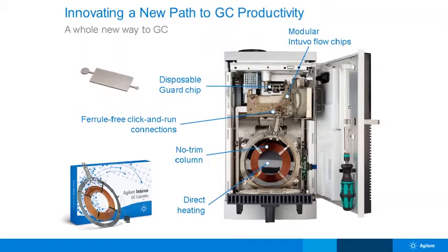And clearly this is the GC that we go to where ease of use is paramount because there's no cutting of columns, no ferrules needed here. But additional to that, when fast analysis is needed, because if you can heat at 250 degrees C per minute and also cool from 450 to 50 degrees C in less than 3 minutes, you can see why this GC has some unique abilities. Over and above that as well, we have a disposable guard chip because this column can't be trimmed.